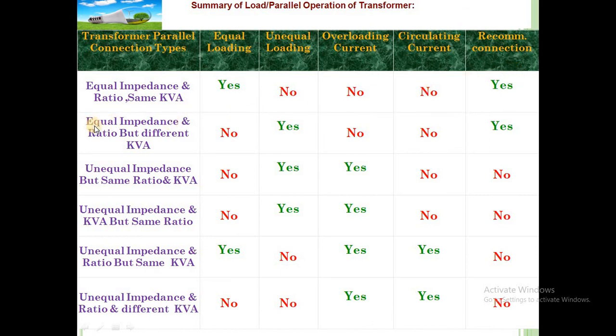Now second case, equal impedance and ratio but different kVA, means equal impedance आहे, ratio सुद्धा equal आहे but kVA rating different आहे. So what will happen? Equal loading will not be there, so unequal loading will be there. सपोज इक्वल इम्पिडन्स असतील, केव्हीए डिफरंट असेल, सो अनइक्वल लोडिंग होईल दोन्ही ट्रान्सफॉर्मरचा. And overloading current will not be there, circulating current will not be there, and yes it is a recommended connection, means केव्हीए रेटिंग जरी सेम नसेल तरी पॅरलल ऑपरेशन होऊ शकतं आणि it is a recommended connection.